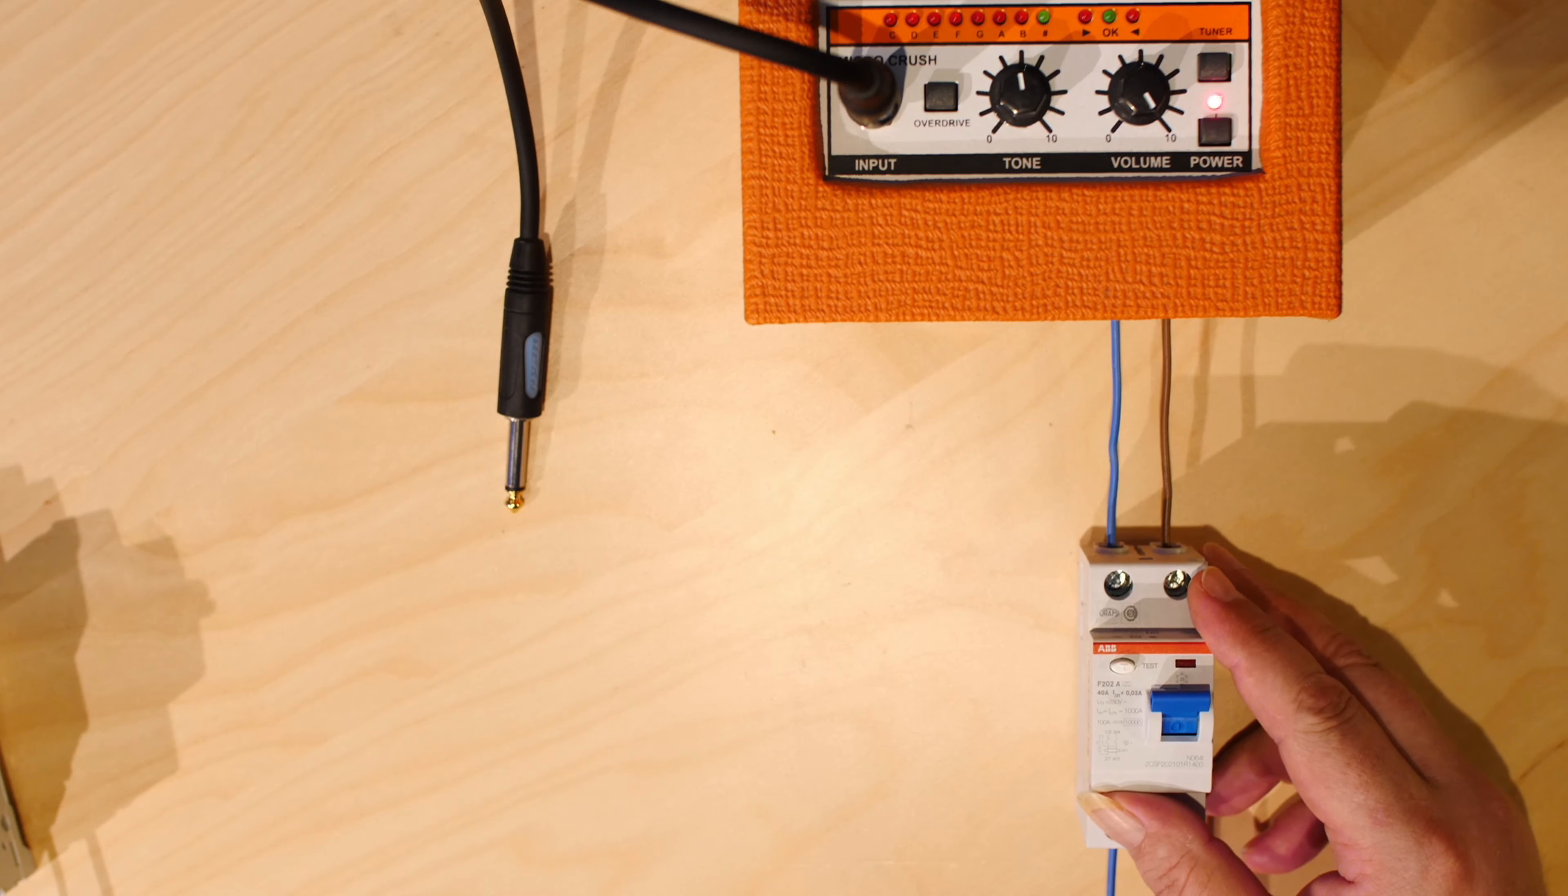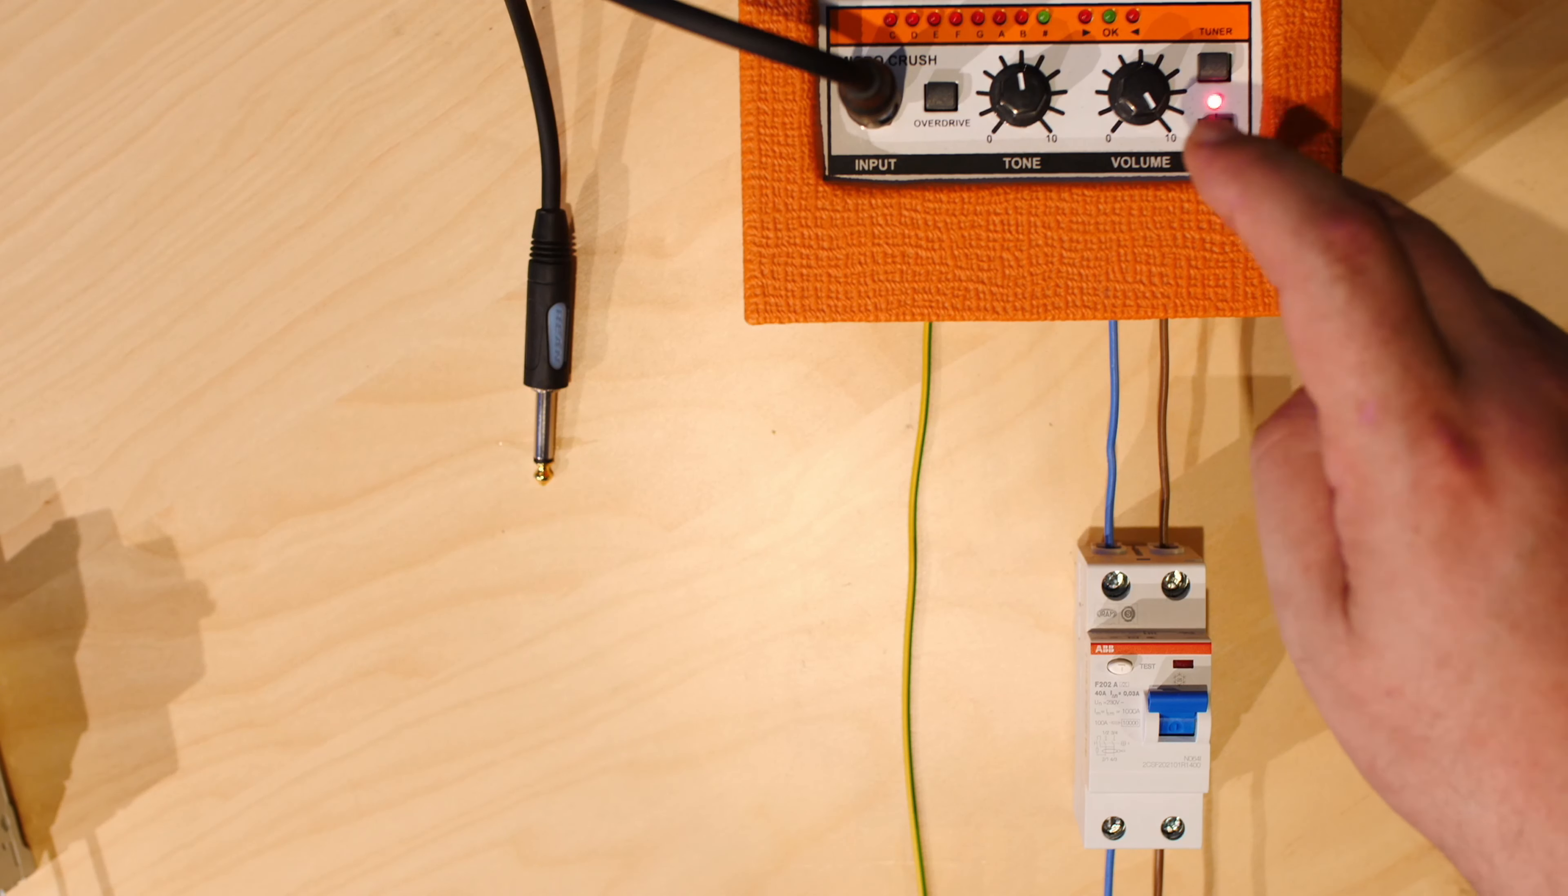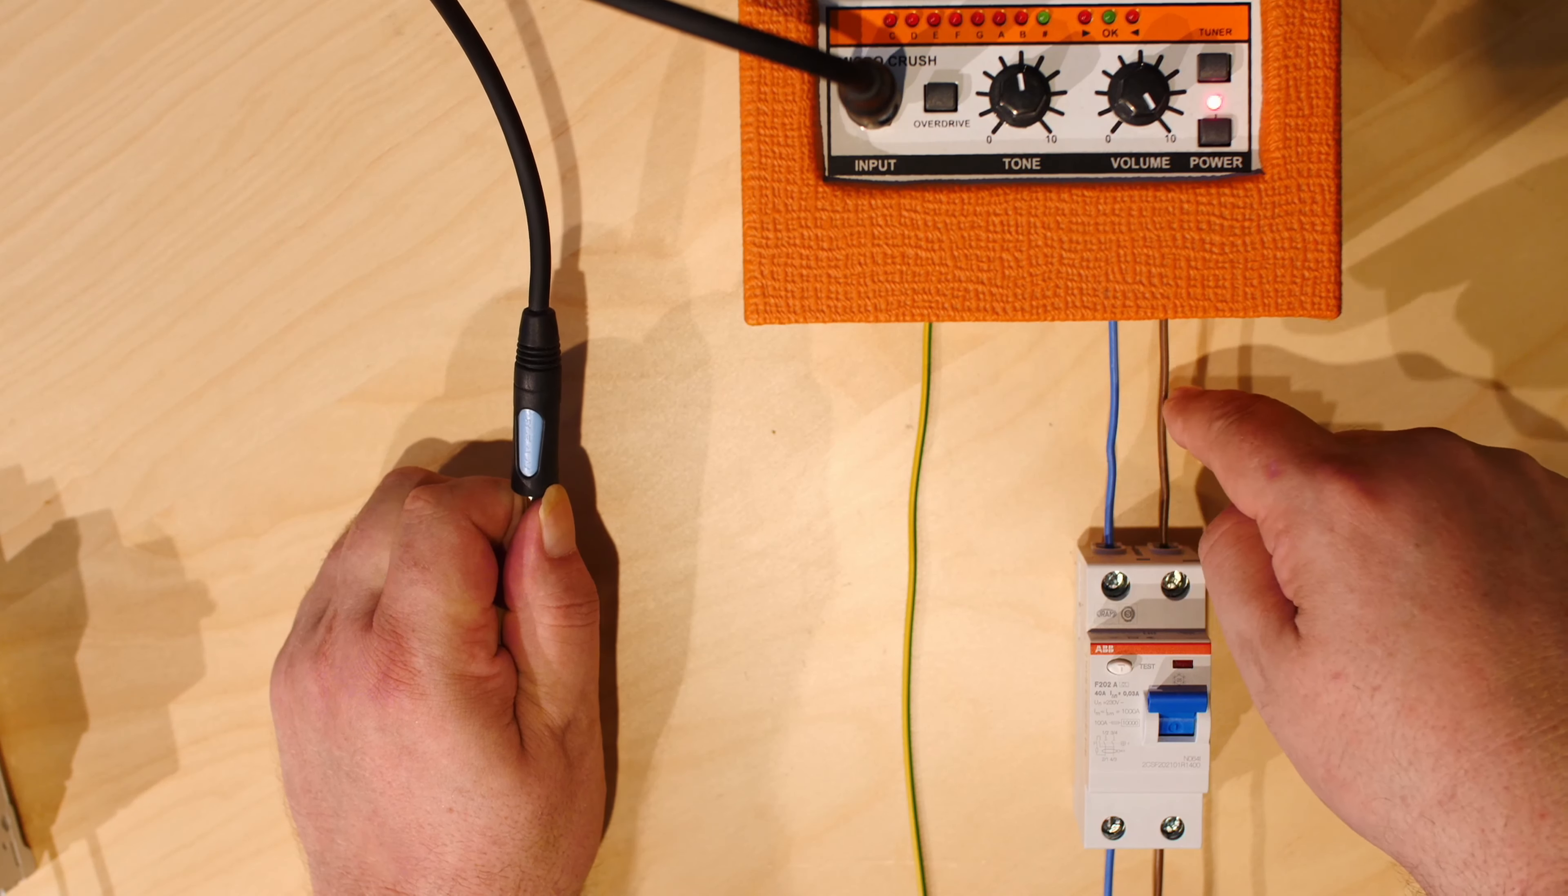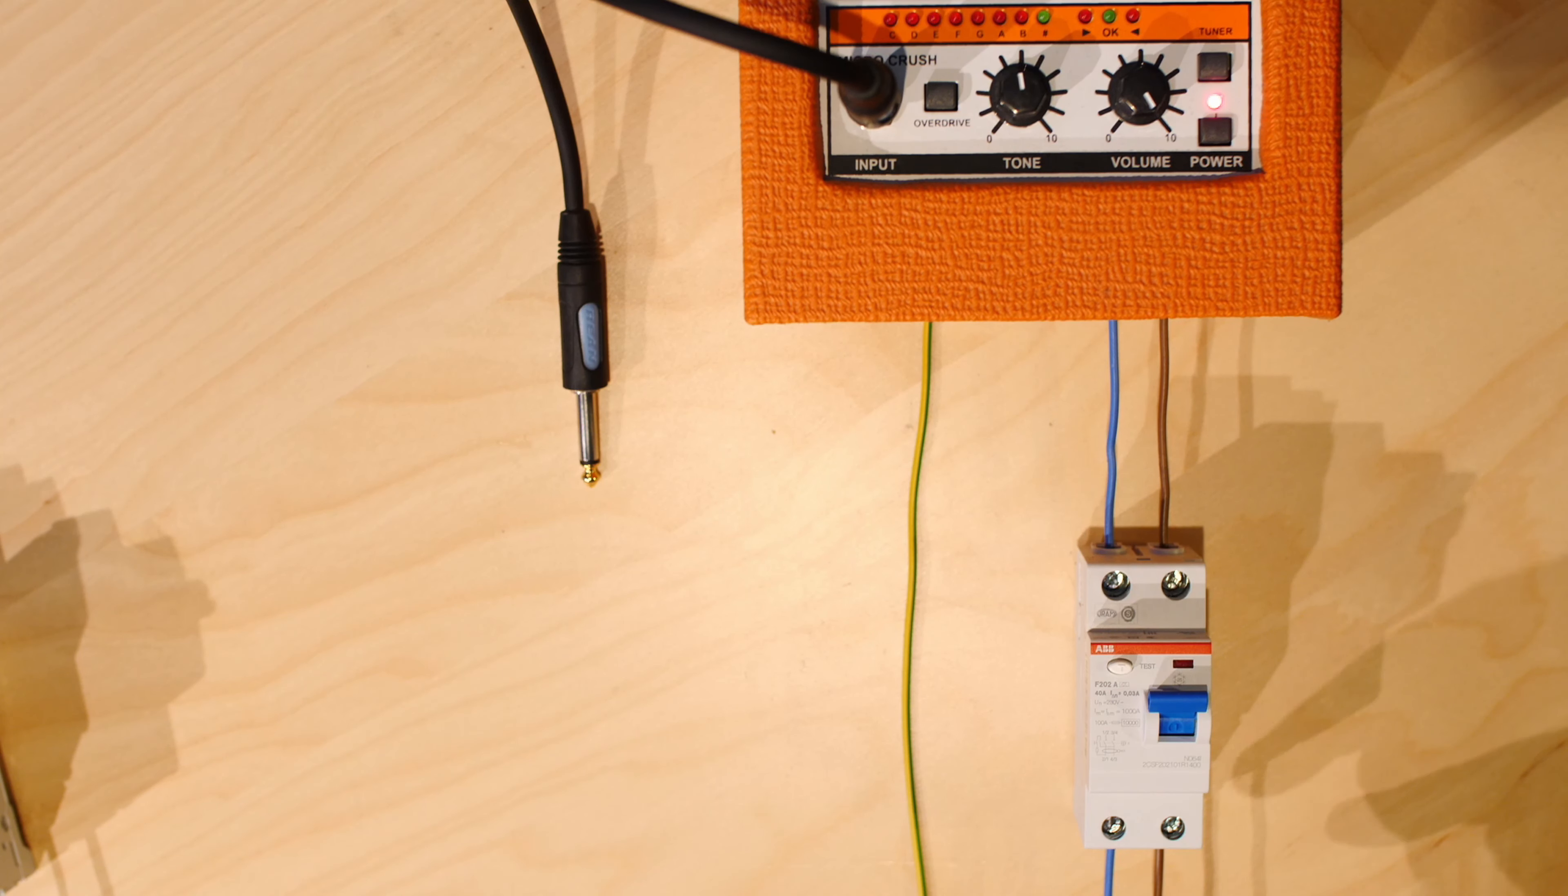So, this here is an RCD, a residual current device, and what does this residual current device do? Let's just assume that we have the proper three wire. So, if there is a massive current, because of an electrical fault inside your guitar amp, or because you are touching here, whatever, if there is something going on, then the current will flow into the amp, and, for example, through your fingers, to earth. And this device measures the difference between brown and blue, in this case, brown and blue wire. So, usually, if nothing is wrong, everything is fine, and the amp is consuming like two ampere electrical current, then there will be two ampere flowing into the guitar amp, and back through the blue wire, also two amps. So, it will basically be the same current on both.